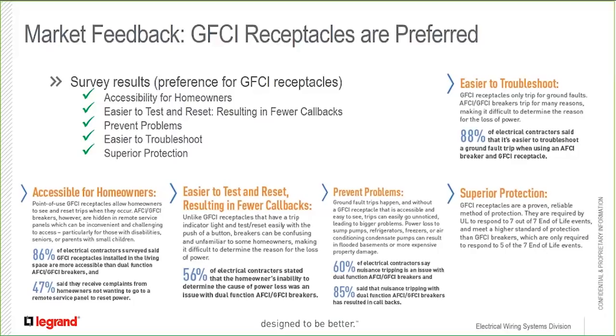GFCI receptacles are preferred because they're easier to test and reset, resulting in fewer callbacks for the contractor. GFCI receptacles have a trip indicator light, and they test and reset easily with a push of a button. Circuit breakers are very confusing and unfamiliar to many homeowners, making it difficult to determine the reason for the loss of power. 56% of electrical contractors surveyed stated that the homeowner's inability to determine the cause of power loss was an issue with dual function AFCI, GFCI circuit breakers.